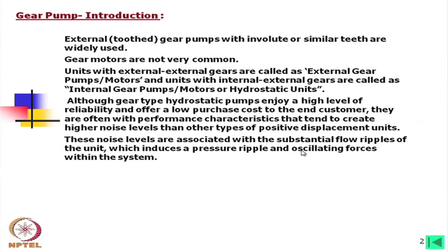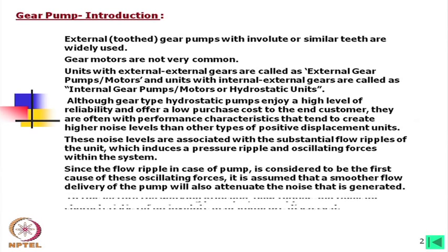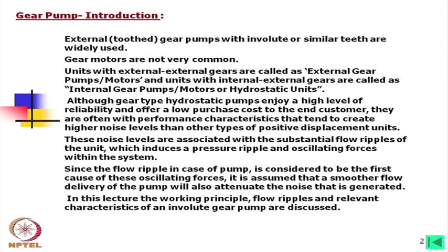These noise levels are associated with the substantial flow ripples of the unit, which induce a pressure ripple and oscillating forces within the system. Since the flow ripple in the case of a pump is considered to be the first cause of these oscillating forces, it is assumed that a smoother flow delivery of the pump will also attenuate the noise generated. In this lecture, the working principle, flow ripple, and relevant characteristics of an involute gear pump are discussed.